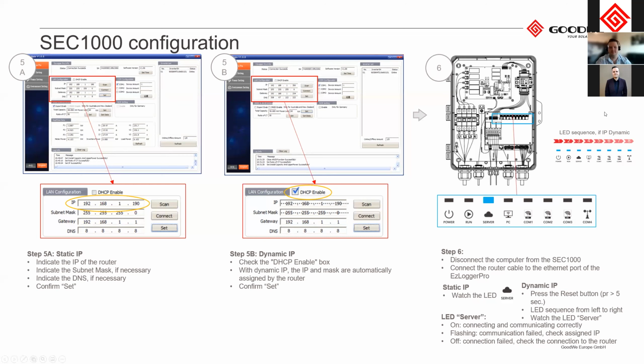Another alternative is to set this to dynamic, so the DHCP. If you don't want to set it through the interface, you can just press the reset button. As long as you press it for less than 5 seconds, so I normally just say press and hold it for 3 seconds. You let go of that, you'll see the LED sequences go from left to right. Then we know we're in dynamic IP. Then you can just unplug your LAN cable, plug it into the computer, and you should see your server light go on solidly.